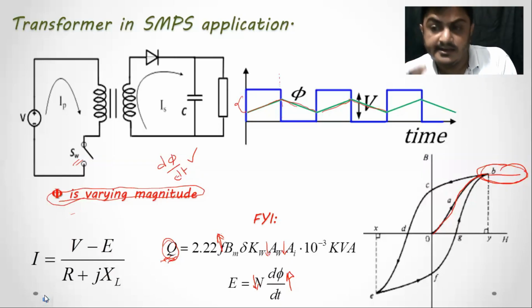Remember, in aerospace applications also, they are not operated at low frequency, they are operated at high frequency, for the same reason. The intention is to increase the frequency so that the size of magnetics comes down, the size of conductor is reduced, and ultimately the transformer or any other inductive devices connected in the supply system are reduced in size.